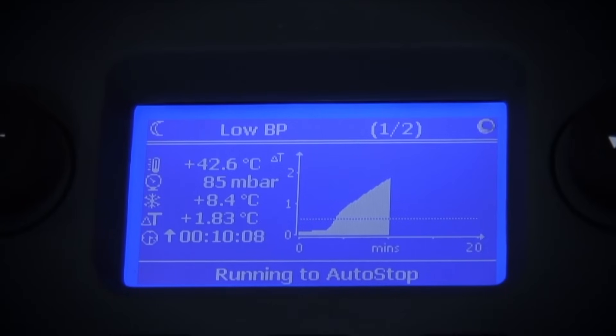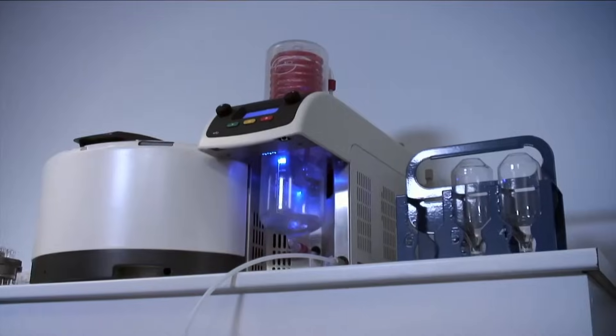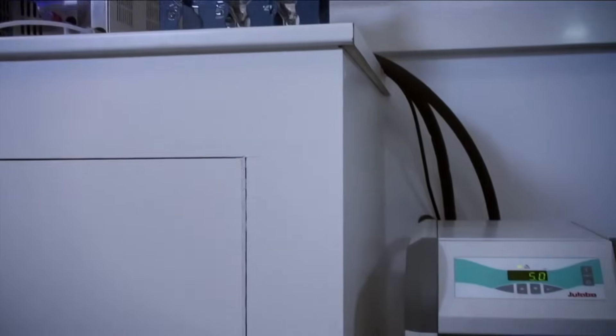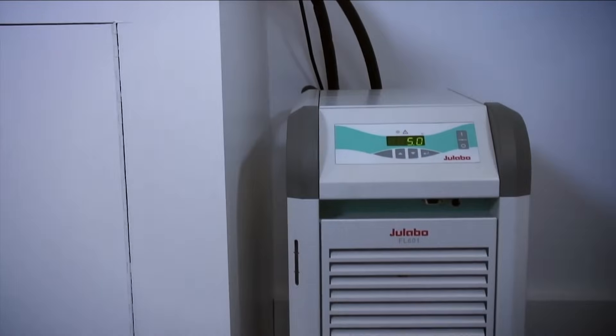You can monitor the progress of evaporation using the delta-t graph that calculates the difference between the coolant temperature entering and leaving the cold trap. When this value approaches zero, evaporation is close to an end.